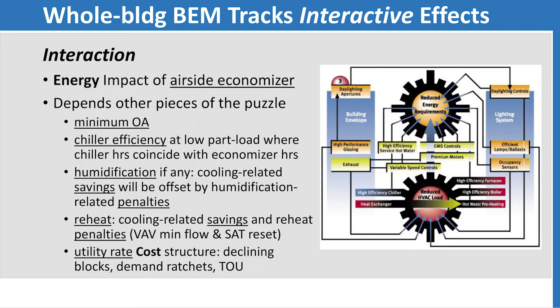outside air in the first place. And does that code minimum change with CO2 sensing? If there's relatively limited amounts of outside air, then obviously the range of operation for the airside economizer is significant, and therefore its impact will be. But if we're in a building like a lab or a hospital where there's a greater amount of constant base load, if we might call it that, code level outside air, then the economizer doesn't have as much range of operation, won't have as much influence.